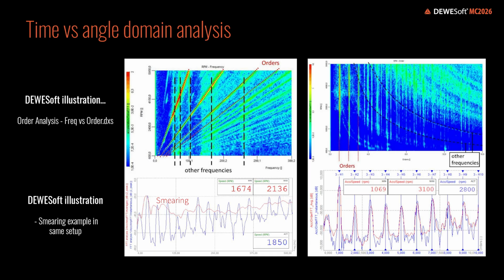One of the things we are using to do order analysis is tracking the rotation speed, and we do that in order to make sure that we can look at the signals and the content of the harmonics, no matter the speed variations you have. And this is the basic concept for using what we call order tracking or speed tracking analysis, where in normal analysis you're having a frequency spectra.